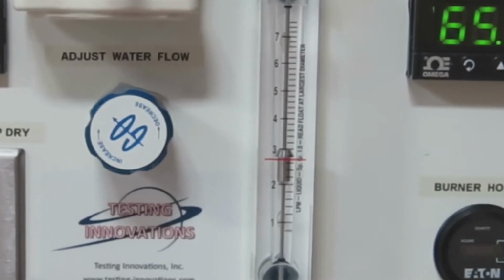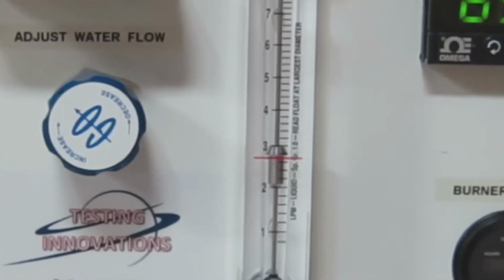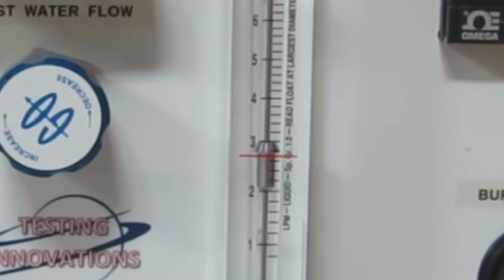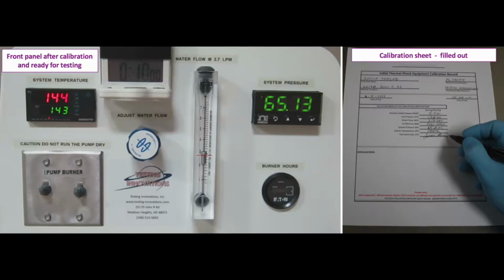Always keep the water flow rate indicator within 1/16 of an inch of the 2.7 liters per minute target line. As long as your water flow rate is right on the 2.7 and your target values for pressure and temperature are still within tolerance, you are able to continue testing. If not, you must stop.